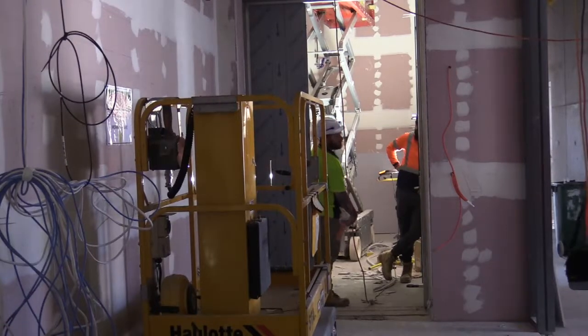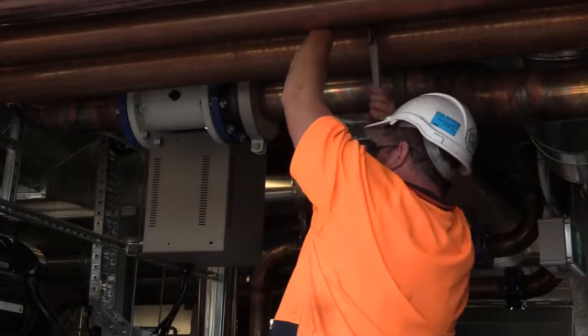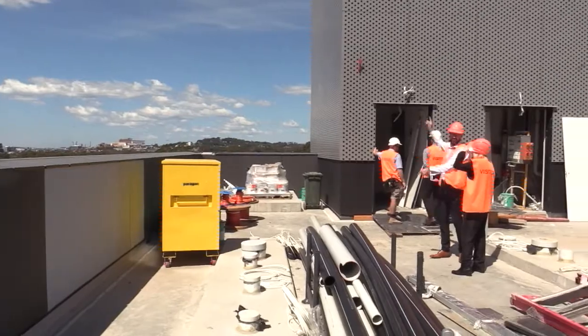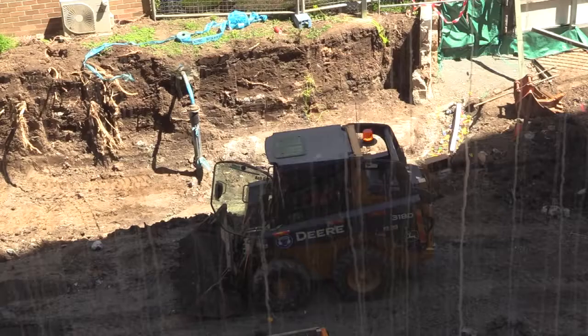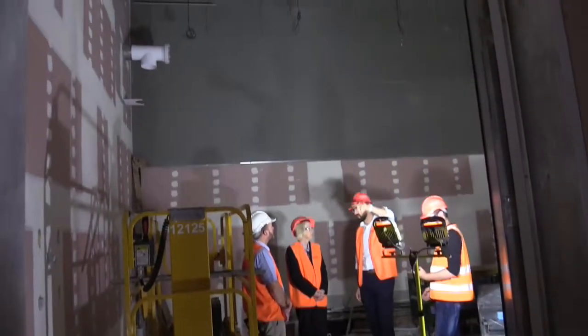The 3-level building will have teacher labs, classrooms, and a seminar hall that will be occupied by teachers, staff, and researchers by mid-December. Until then, the builders need to ensure the microscopes are housed in a space with no sound, vibration, oscillation, or electromagnetic interference. Dishwashers aren't found in the building, and elevators are at least 25 meters away from the microscopes.